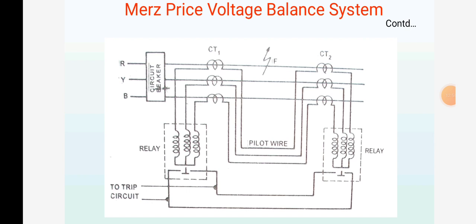In case of internal faults, secondary voltages of CTs become unequal and circulating current flows through the pilot wires and operating coils of the relays. This figure shows the connections of the Merz-Price voltage balance scheme for all three phases of the line.